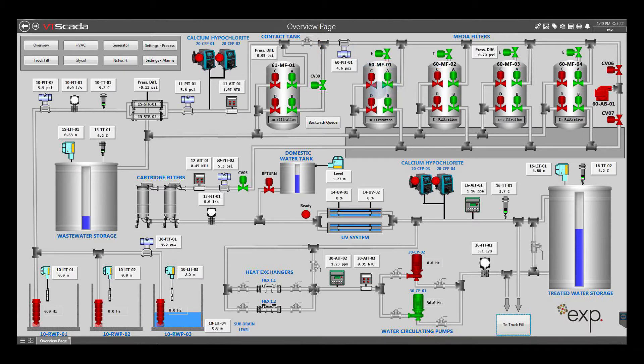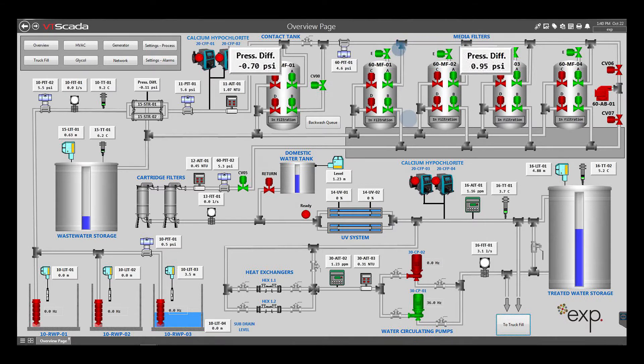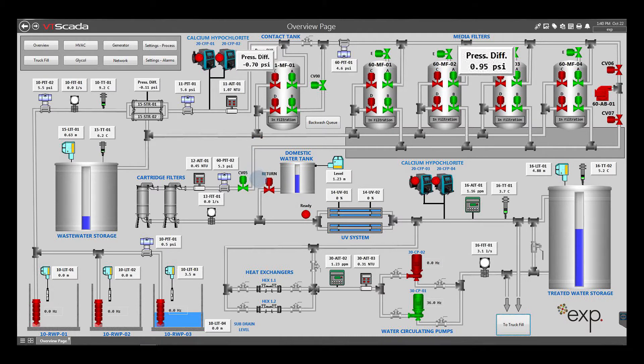The pressure is measured before and after the media filters. The pressure differential indicates if the filter needs to be backwashed of the precipitates. This will trigger an automatic backwash. The backwash goes to the wastewater storage tank. Also, each filter will be automatically backwashed after its production time.